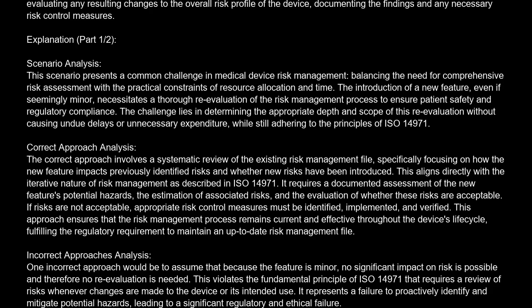Incorrect approaches analysis. One incorrect approach would be to assume that because the feature is minor, no significant impact on risk is possible, and therefore no reevaluation is needed. This violates the fundamental principle of ISO 14971 that requires a review of risks whenever changes are made to the device or its intended use. It represents a failure to proactively identify and mitigate potential hazards, leading to a significant regulatory and ethical failure.